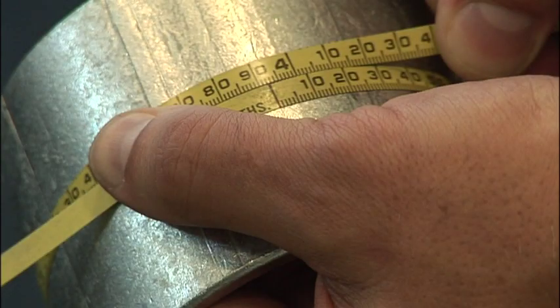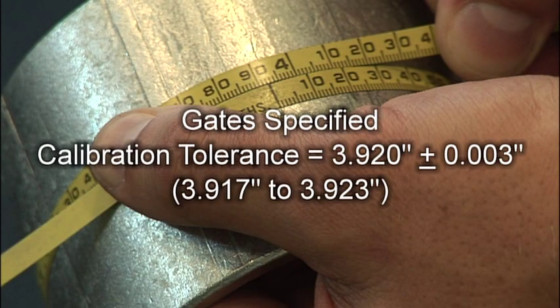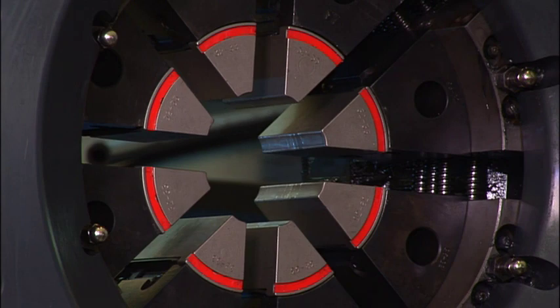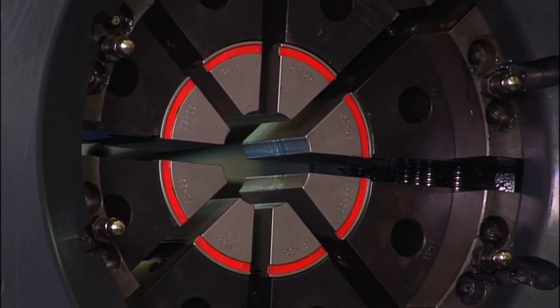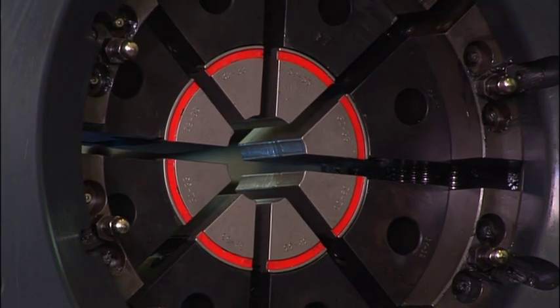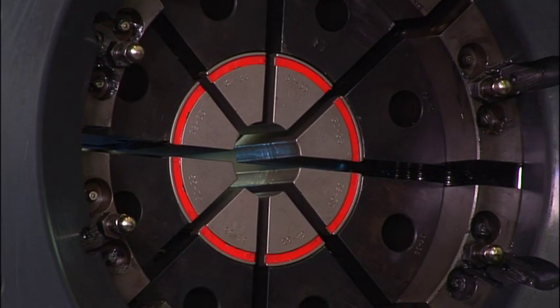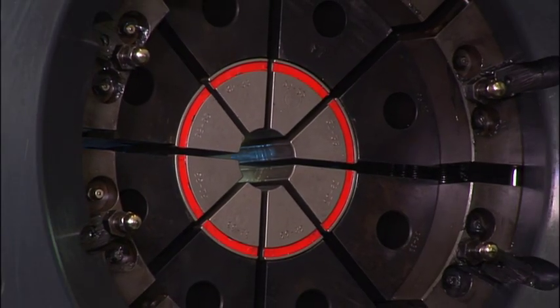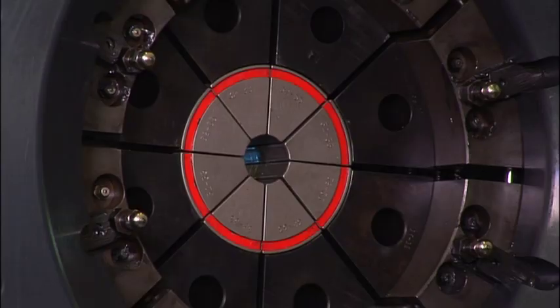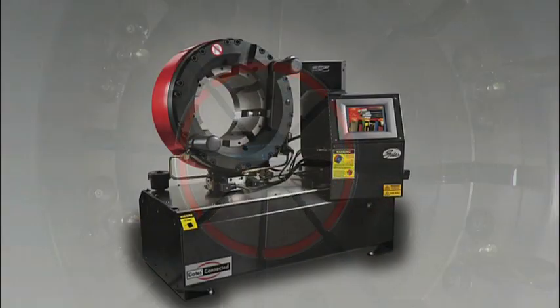The crimp diameter must measure 3.92 inches plus or minus 0.003 of an inch. The acceptable range is from 3.917 inches to 3.923 inches. If the crimp diameter is within the acceptable range, no adjustment is necessary. If the crimp diameter is not within the acceptable range, the crimper must be calibrated. Follow the procedure outlined earlier for calculating a new offset value and new adjusted setting value and enter the new numbers. Repeat the calibration steps until the published crimp diameter is achieved. The crimper is now calibrated.